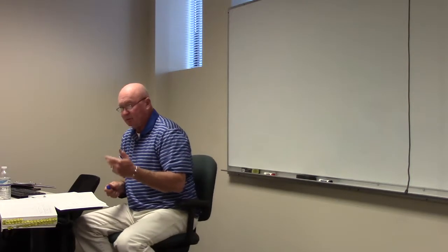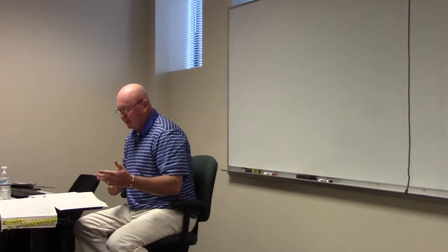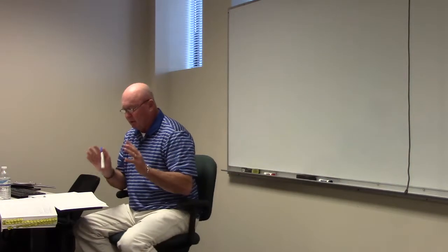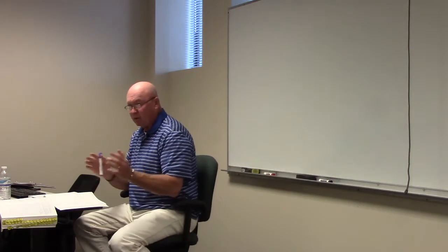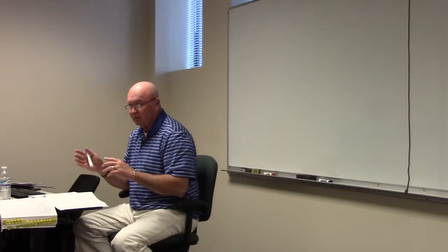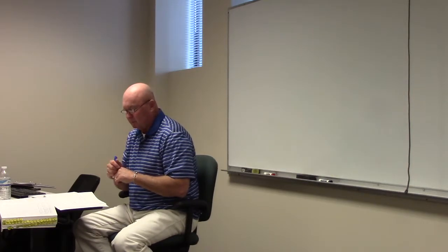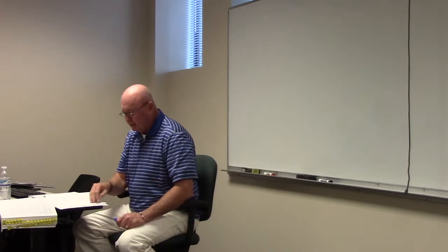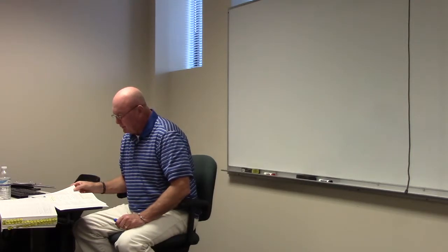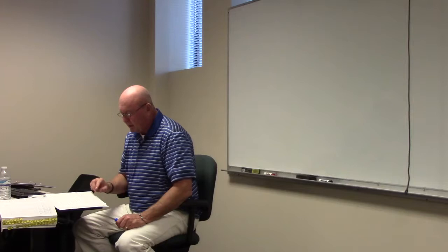So it says it's a 20 amp, so 1.75 times 20 is 35 amps. That's just the fuse size. But our load as far as line A and C is what? Is it 35 or is it 20? It's 20, isn't it? As shown. A neutral? No, no neutral. Okay. All right, it says there is a three-phase, 5 horsepower fan.